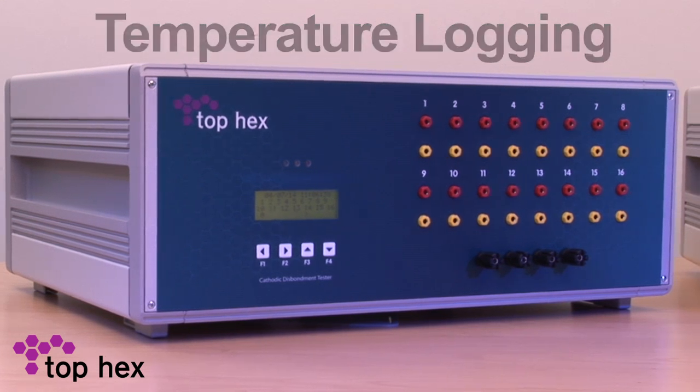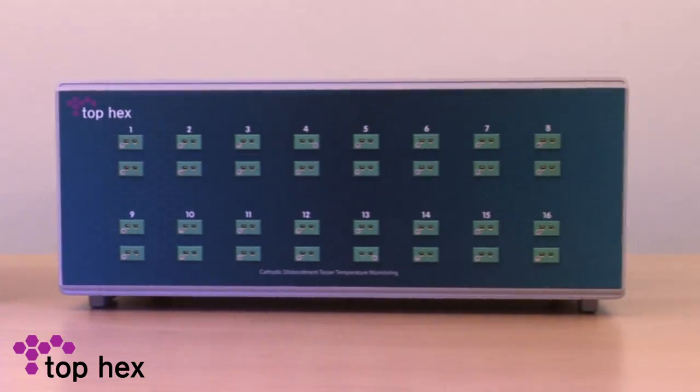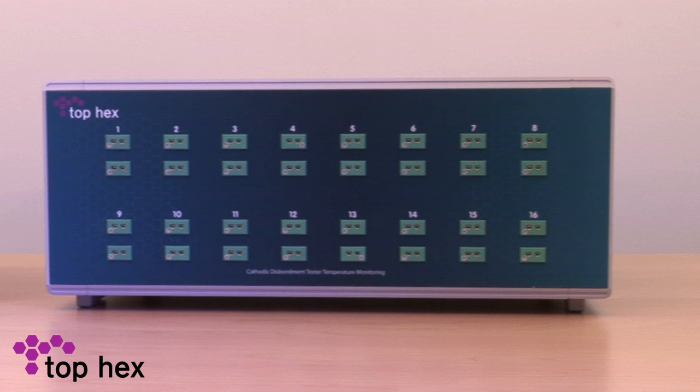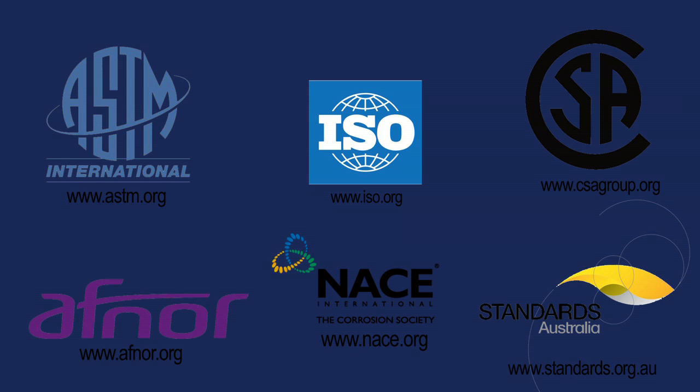The temperature logging module simplifies the process of recording temperatures during a cathodic disbondment test. This is of particular benefit when the test is carried out at an elevated temperature, which is a requirement of many test specifications.